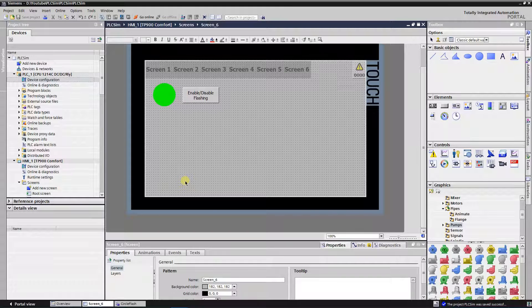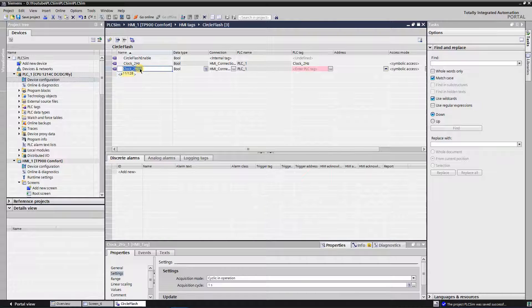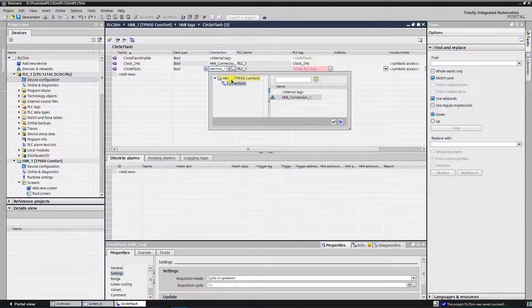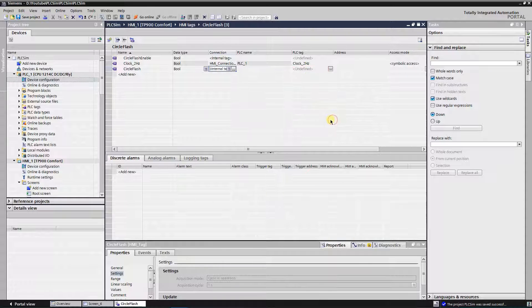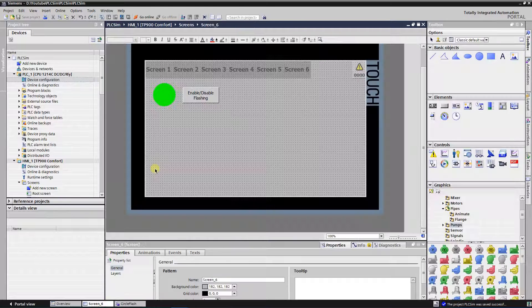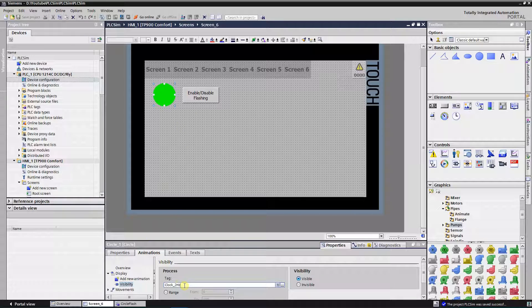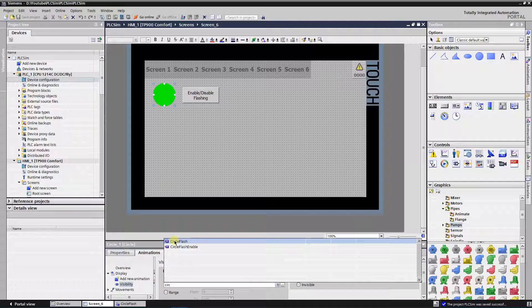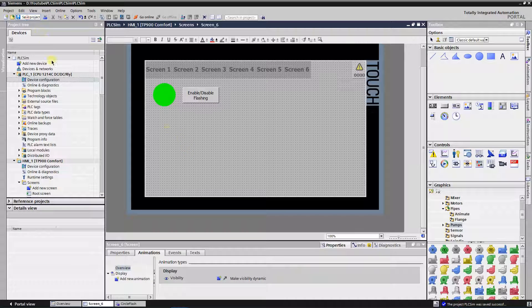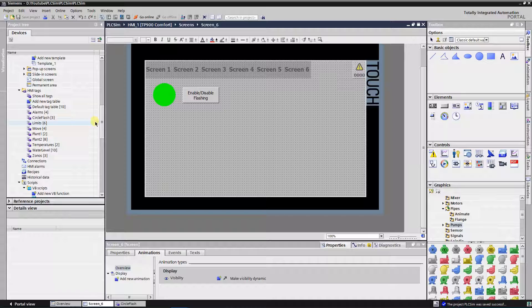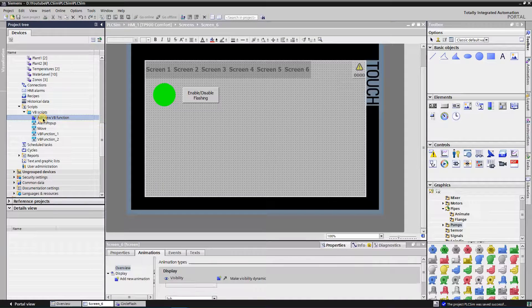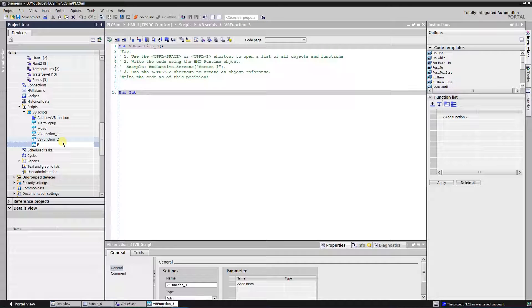Let's add some more control. From this point VB scripting comes to help. Let's create a setup where flashing is connected to a tag. Open the tags table and create a new internal tag of type bool. Switch to the screen with the circle. Select visibility from the animations of the circle and replace the connected tag with the newly created one. Create a new VB script. I want blinking to be active only if it is enabled, so for that purpose I will use an if-else statement.